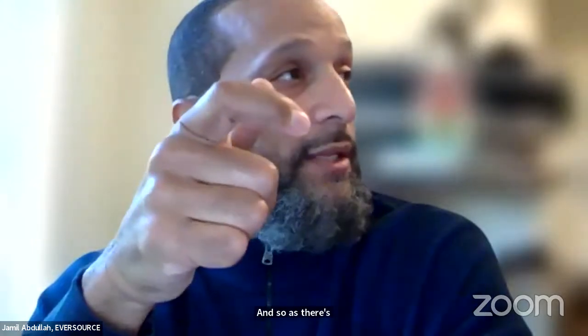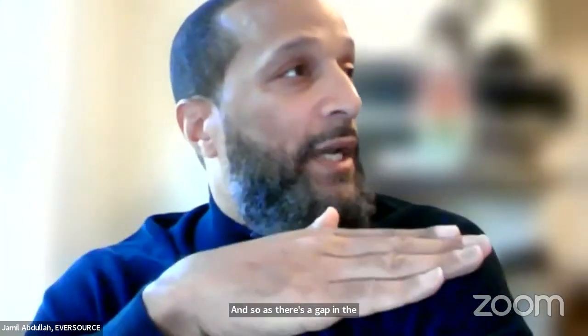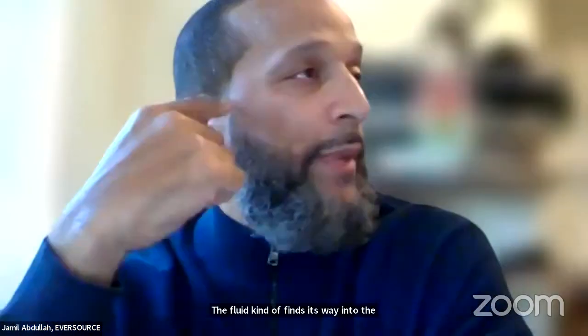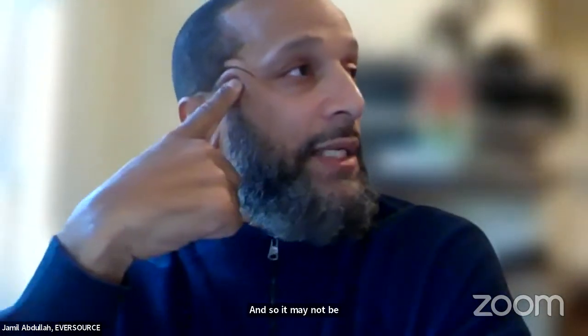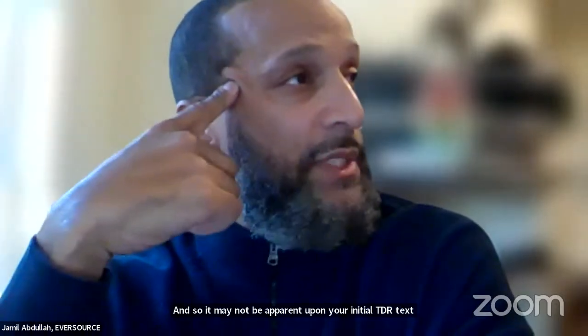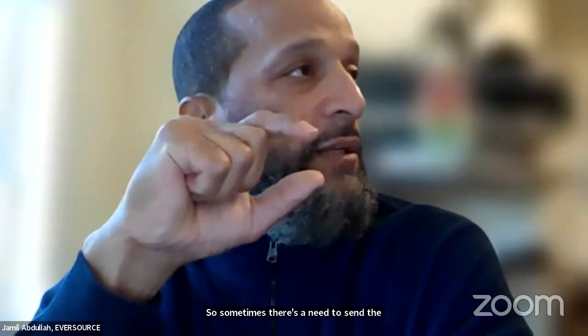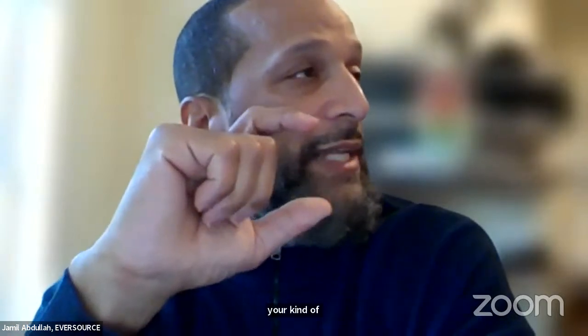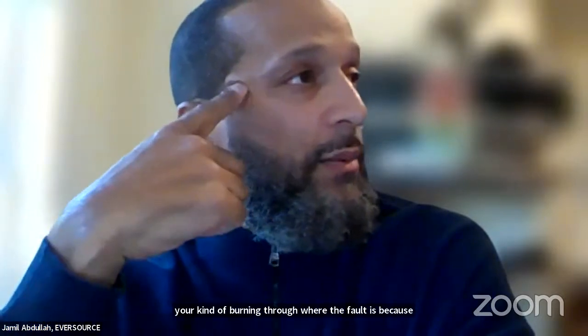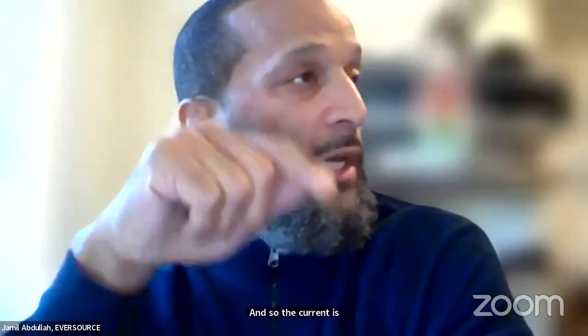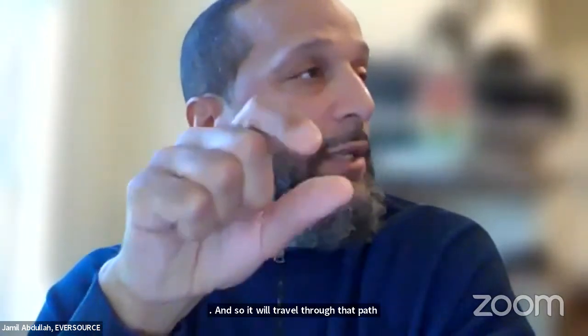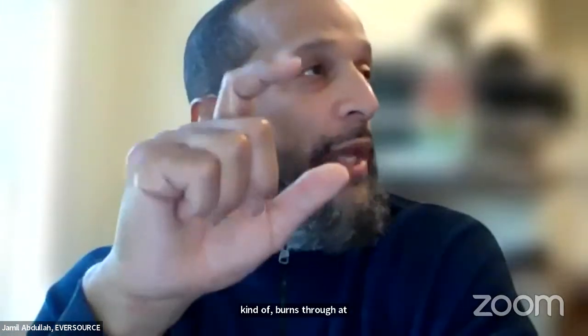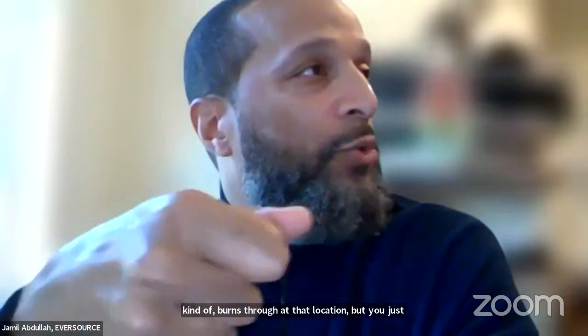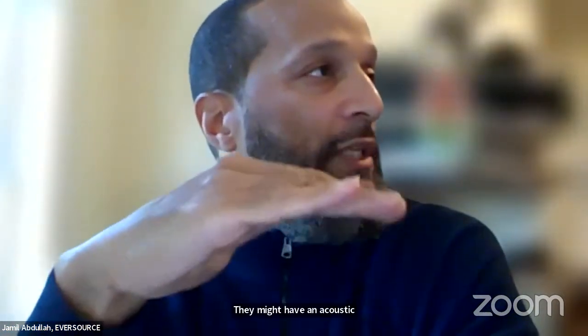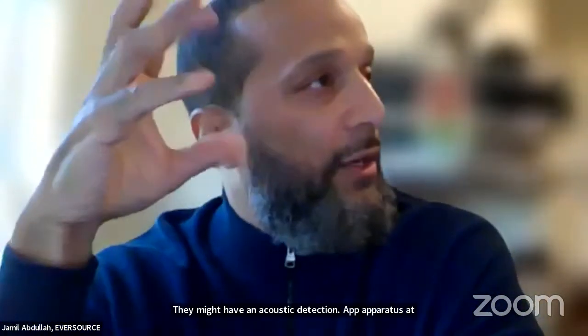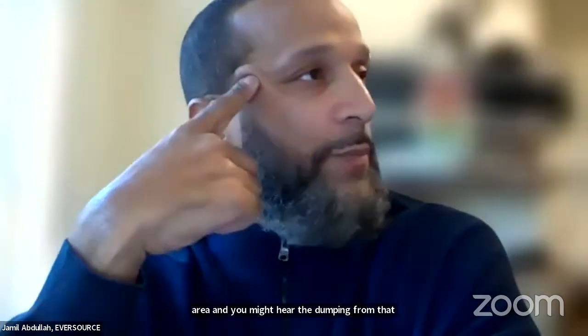And so as there's a gap in the conductor itself, the fluid finds its way into the conductor. And so it may not be apparent upon your initial TDR test, or if you try to bridge from the station ends. So sometimes there's a need to send a signal so that you're burning through where the fault is, because that's the weak point of the conductor. The current is looking to get to ground, so it will travel through that path and burns through at that location. You just call it thumping, because sometimes when you're looking for a fault, they might have an acoustic detection apparatus at the street surface with an operator walking the area, and you might hear the thumping from that arc that's being sent.